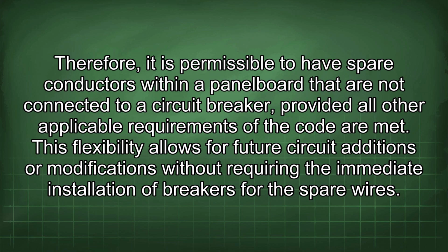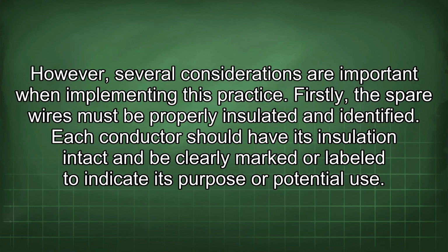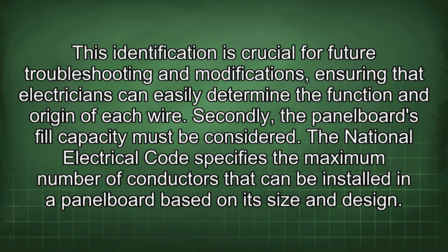This flexibility allows for future circuit additions or modifications without requiring the immediate installation of breakers for the spare wires. However, several considerations are important when implementing this practice. Firstly, the spare wires must be properly insulated and identified. Each conductor should have its insulation intact and be clearly marked or labeled to indicate its purpose or potential use.